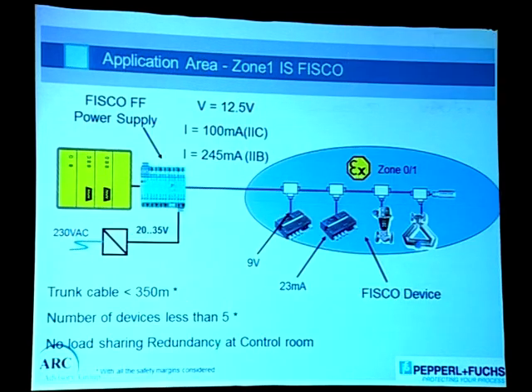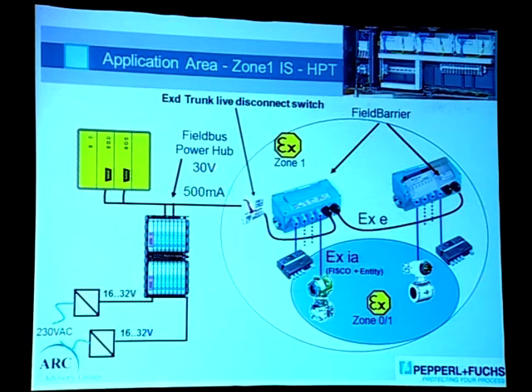Compared to the previous method, intrinsic safety starts from the control room, so the trunk as well as the spur cable, everything is intrinsically safe. But it has so many limitations. The second method provides all the advantages, but we still have certain limitations, especially the trunk cable, which goes from the control room all the way to the field. We have certain checks and marks, and it has to follow certain guidelines and standards. But unfortunately, if the technician is not trained enough, or somebody pulls the trunk cable, that's not going to give good results.